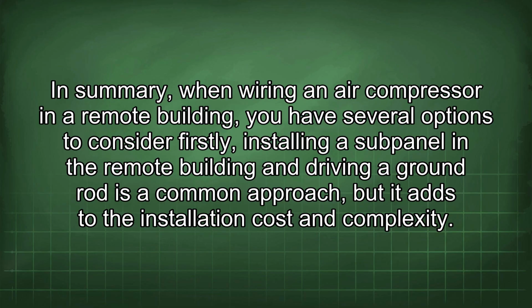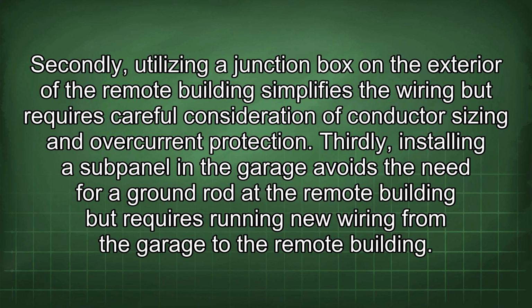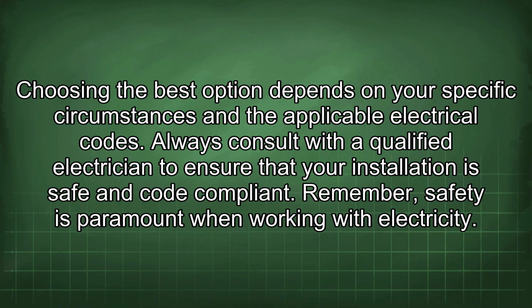In summary, when wiring an air compressor in a remote building, you have several options to consider. Firstly, installing a subpanel in the remote building and driving a ground rod is a common approach, but adds to the installation cost and complexity. Secondly, utilizing a junction box on the exterior of the remote building simplifies the wiring but requires careful consideration of conductor sizing and overcurrent protection. Thirdly, installing a subpanel in the garage avoids the need for a ground rod at the remote building but requires running new wiring from the garage to the remote building. Choosing the best option depends on your specific circumstances and the applicable electrical codes.